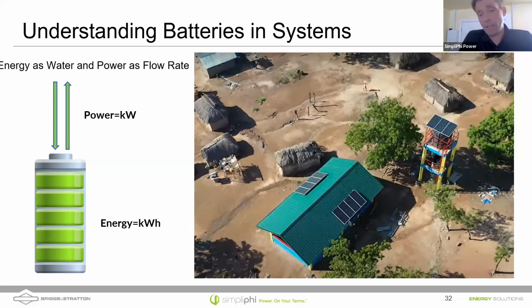Our batteries have a fairly high power rating. It's a C/2 discharge cycle, which means you can take all the energy out of the battery in 2 hours. The same with charging it, you can charge it in 2 hours. So there's a power limitation on batteries, because all of our batteries are rated at C/2. If you know that you have a 5 kilowatt hour battery with us, the output power of that battery is over 2 hours. So 5 kilowatt hours divided by 2 hours is 2.5 kilowatts. So half of the battery's energy capacity would be its power output.